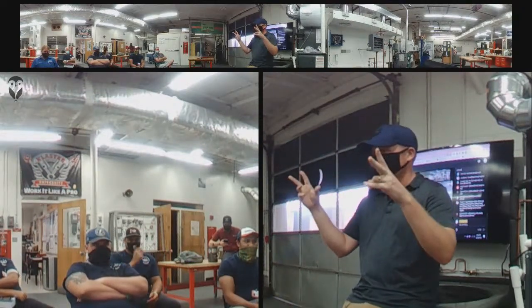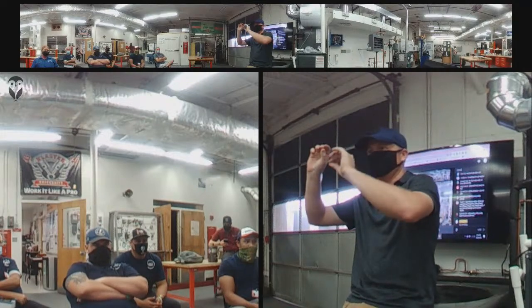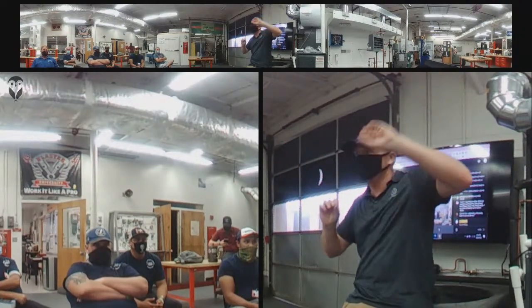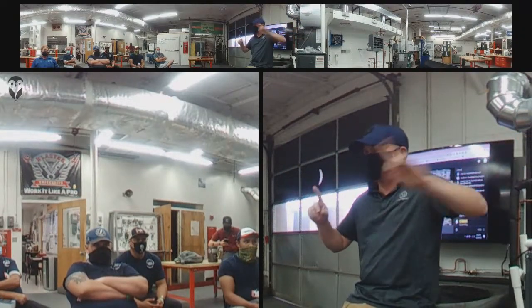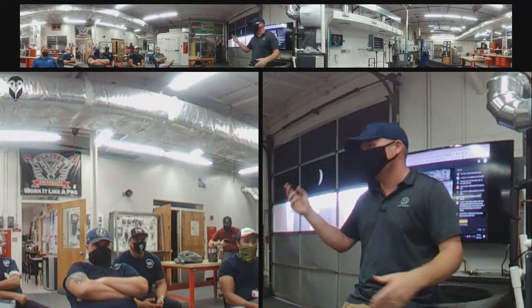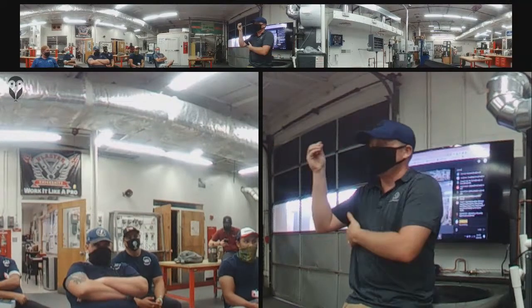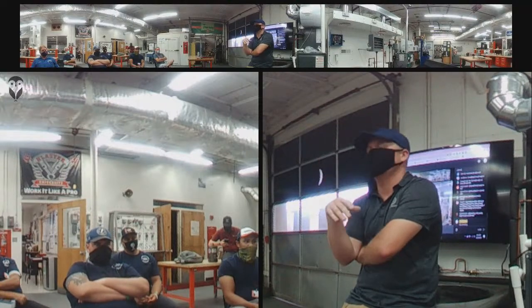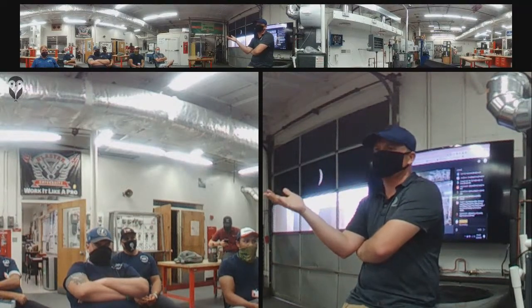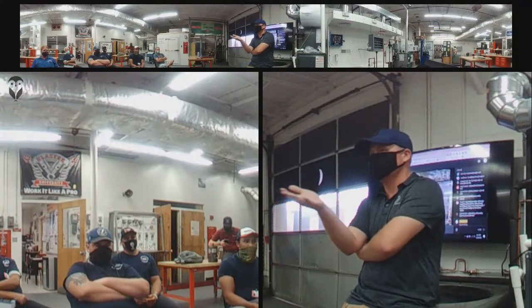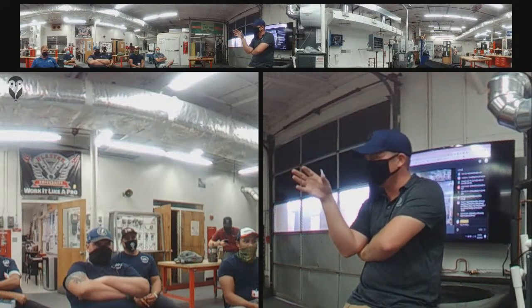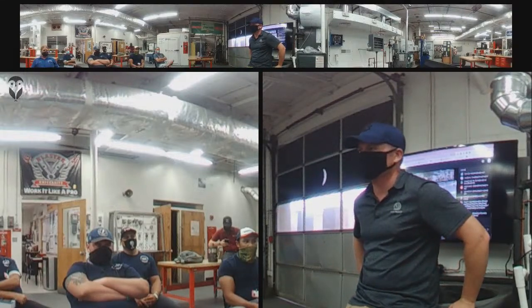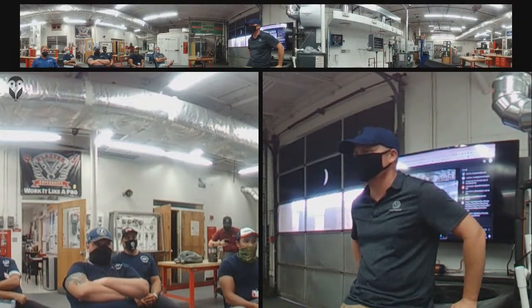G wire. When you have a split system, you've got one cable going inside to your thermostat and one going outside to the condenser. The one going to the condenser doesn't need a G wire because the condenser doesn't have a blower in it. The G wire is specifically for your blower call. In fact, back in the day when you had heat-only furnaces, you didn't always need a G wire. The furnace board would control the blower, so G is one of the newer conductors in the world of controls, because back in the day it was all done by the furnace board.